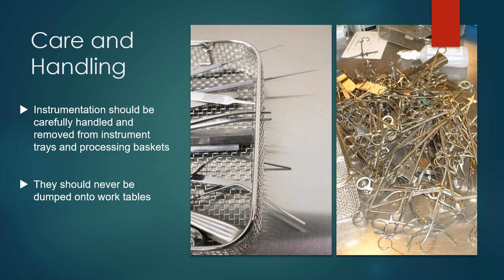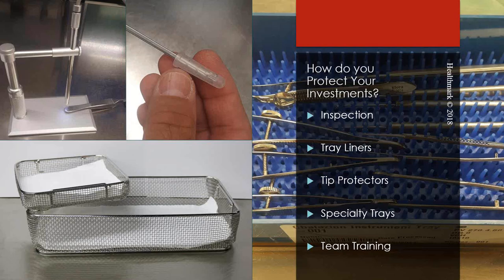Also, organize the basket so things are in the same direction, heavier on the bottom, lighter on top. They should never be dumped onto work tables on the clean side, as you see in the picture on the right. I see all this care being taken on the decontam side, but on the clean side, I'll see a technician actually dump the whole tray that's been nicely organized onto a hard metal surface. This damages all the instruments, as well as damaging them as you're trying to take them out.